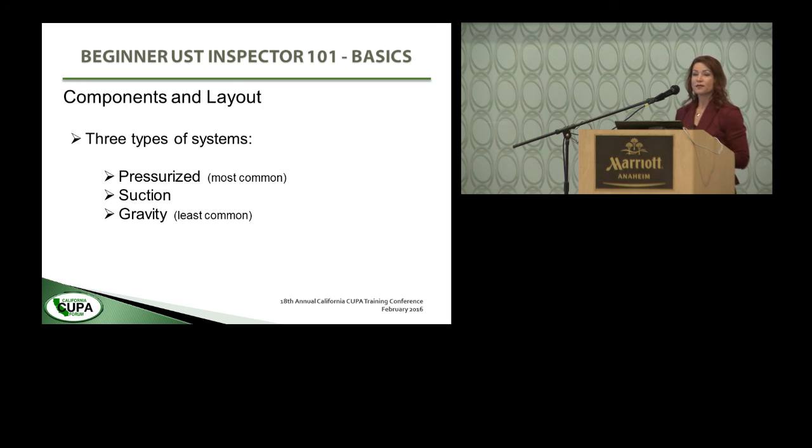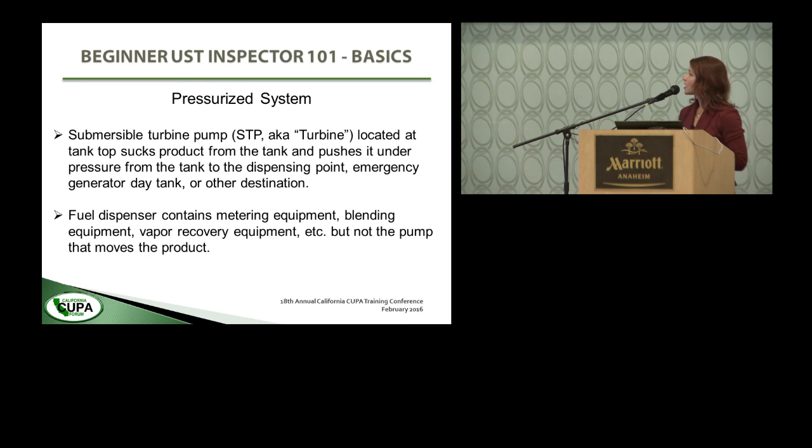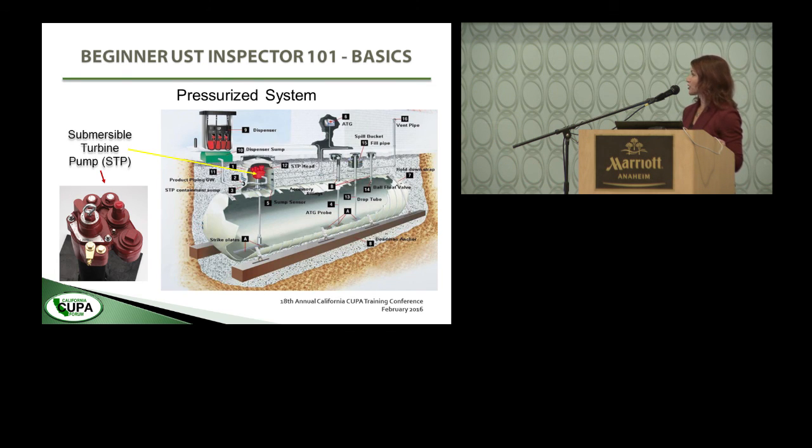There are three types of systems: pressurized, which is the most common; suction; and gravity, which is the least common. In a pressurized system, you have the submersible turbine pump located at or close to the tank top. It sucks the fuel up from the tank and pushes it under pressure through the pipeline to the dispensing location — whether a dispenser, day tank, or other location. So in the dispenser, you're going to have metering equipment and maybe fuel blending equipment, but not the pump that moves the fuel. This is a diagram of a typical pressurized system: the pump — the turbine — is pulling fuel out of the tank and pushing it under pressure up the pipeline to the dispensing location. A submersible turbine pump is what you'd see if you opened up the sump, though when you go out to any typical system it won't look as clean as a brand-new one.